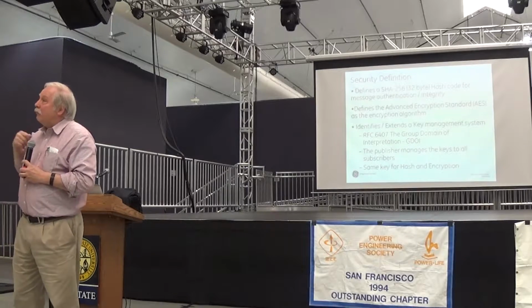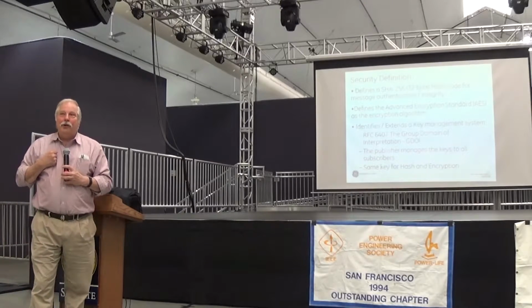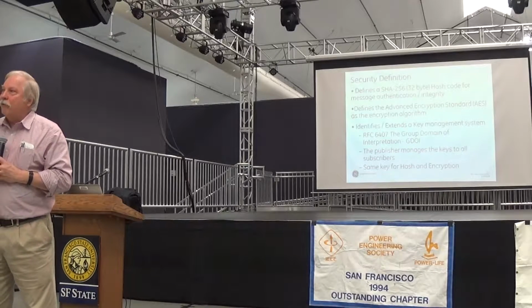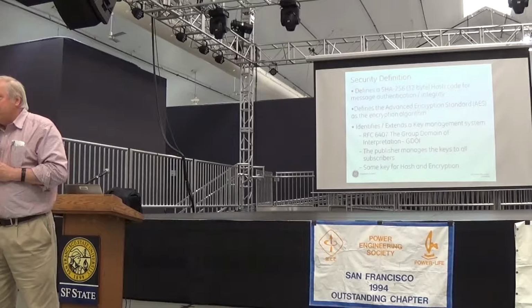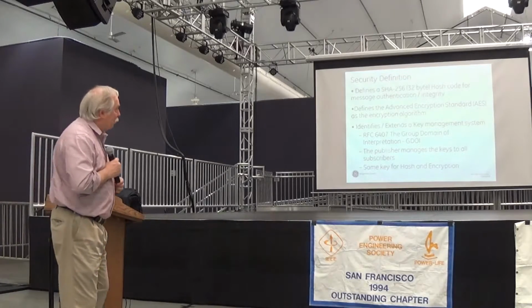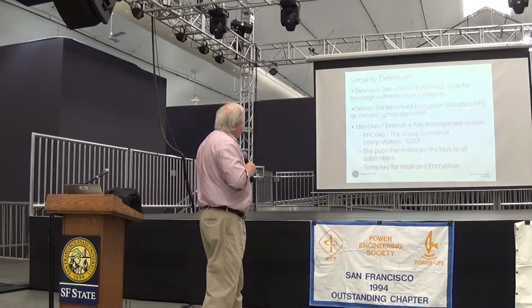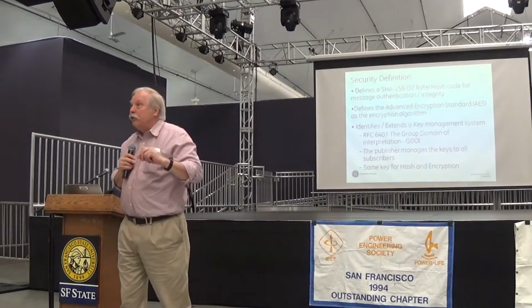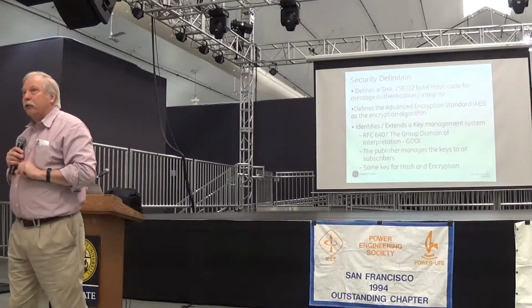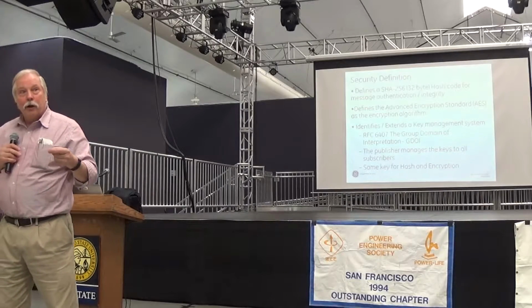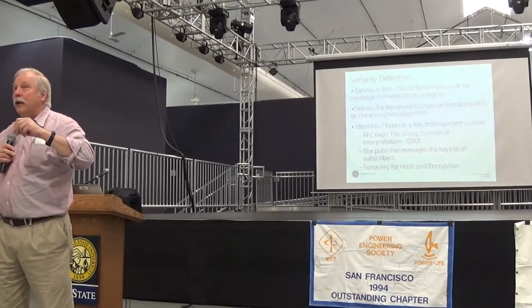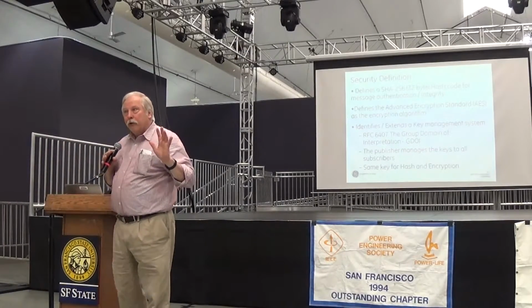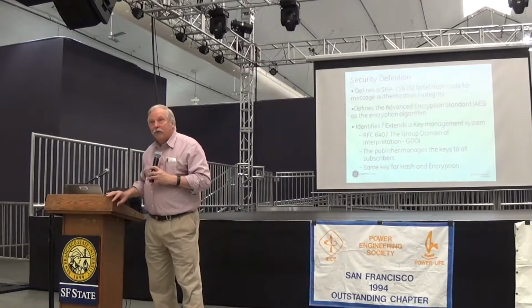The exchange of the keys, however, is done using an asymmetric key. This is what's called a public-private key pair. The exchange is done by an internet standard known as the Group Domain of Interpretation, GDOI, which is IETF 6407. And this standard defines how to exchange keys between all the members of a group. This is all spelled out very, very clearly in the 61850 standard.